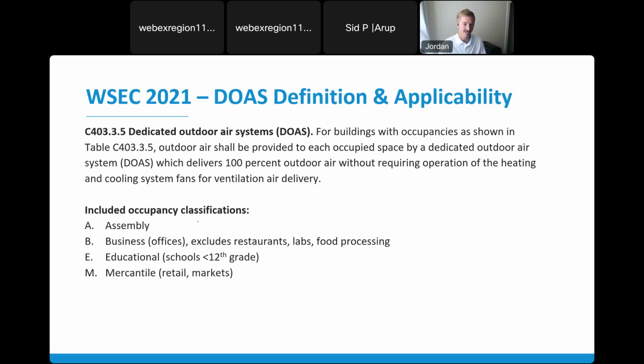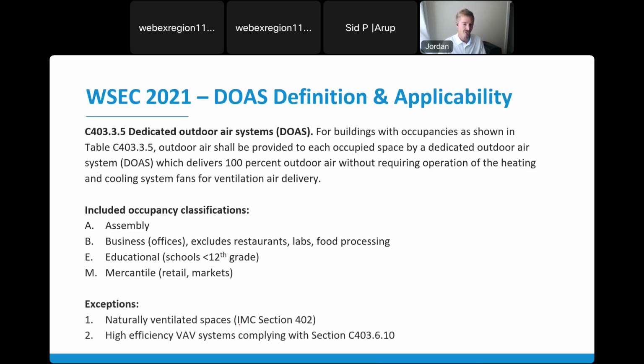So this is a lot. This is a significant portion of all buildings that we think of as commercial buildings. So basically in all of these, in new construction and major renovations or major HVAC changes, DOAS is required. This was also required as of the 2018 version, but there have been a few notable changes in the 2021 version. The exceptions: naturally ventilated spaces are still able to avoid the DOAS, and high efficiency VAV exceptions complying with C403.6.10 are also a notable exception.